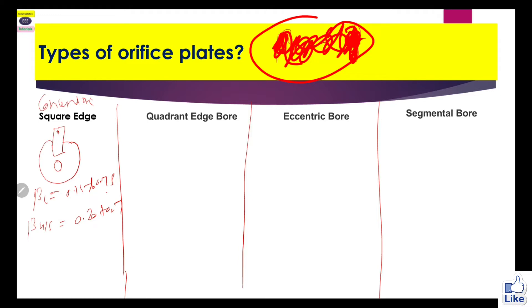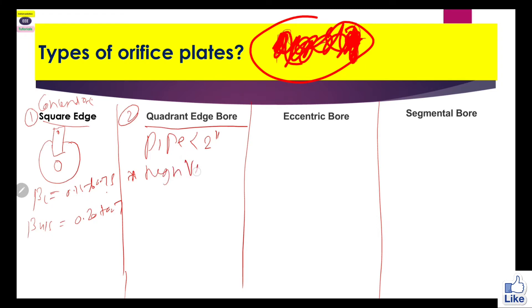The second type is quadrant edge bore. This is used when pipe size is less than 2 inches. It is recommended whenever a high viscosity fluid is used — the quadrant edge bore type orifice plate will be very helpful in such applications.